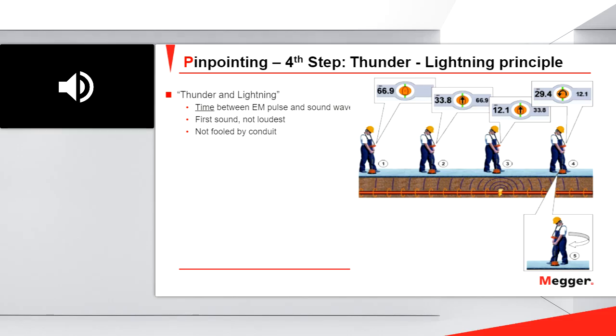As this person walks toward the fault, this number will decrease. And once the person has passed the fault, the number will increase. We call this the thunder and lightning principle, because it's like when you have a storm at night: the first thing you see is the lightning, and then you hear the thunder. For that reason, we call this the thunder and lightning principle.